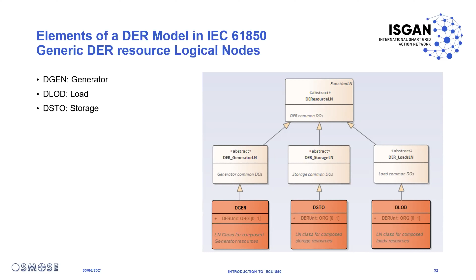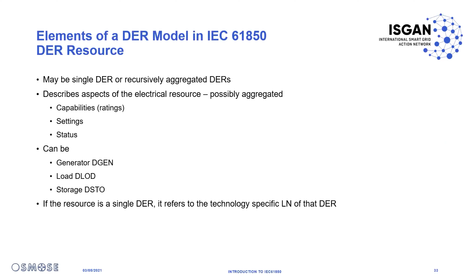What we typically find in this logical node are the aspects of the electrical resource, which could also be aggregated, such as capabilities and ratings, but also settings and status, like whether it is active or not. Such a generic DER resource can be a generator, a load, or a storage, and if it's a DER system hierarchically combined, it can also be a combination of multiple of them. If the DER resource is a single DER, we also have a technology-specific logical node associated, where we find the technology-specific information.